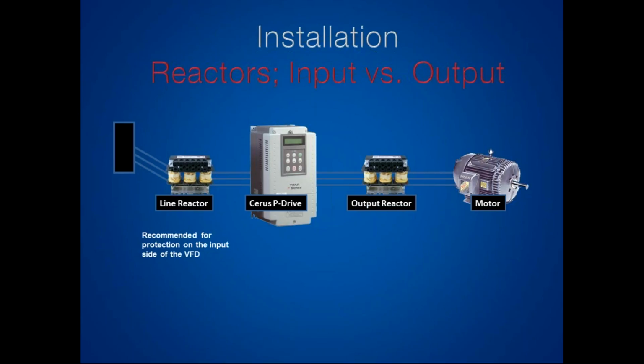Now what you can do with this Cerus P-Drive in order to mitigate those harmonics is have a 3% or a 5% line reactor installed just before the drive, okay? That 3 or 5% line reactor is helping you meet IEEE 519 and it's smoothing out the harmonics. So to be on the safe side, when you're selecting product, I almost always include a line reactor with my drive because I know that engineers want me to meet that IEEE 519. I want to make sure my bases are covered, right? If you don't need it, you don't need it, but it's always a good idea to include it on the front end just to be safe.